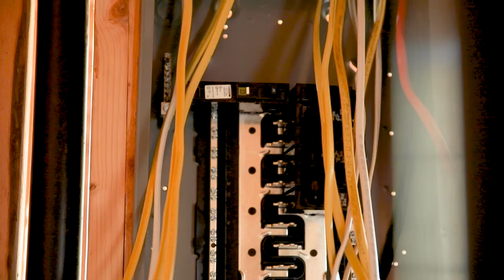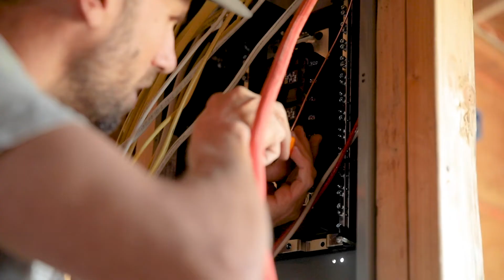So we're going to strip this down. We want to keep things nice and neat in the panel. So I'll start with the hots. Something like that. So we got two. All of these 240s will get both wires because they're adding them up, right? One thing with these is one time I had one where the circuit wasn't working and it was for a stove, and it was because the screw was going down on top of the insulation. So make sure before you tighten it down that you're not going down on the insulation. You don't want extra wire showing, but you also don't want to go down on the insulation. So that's our first one.